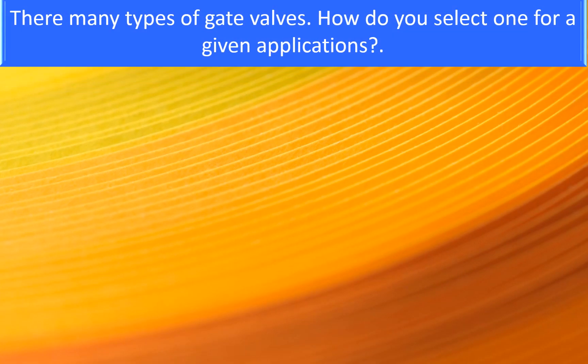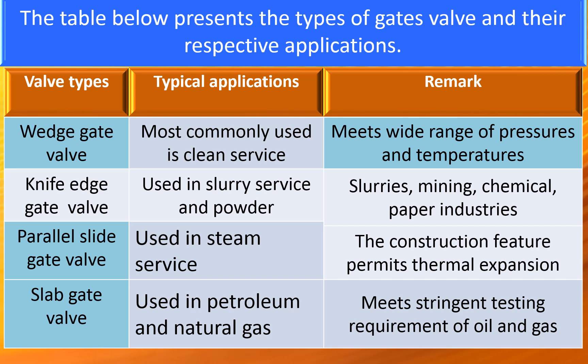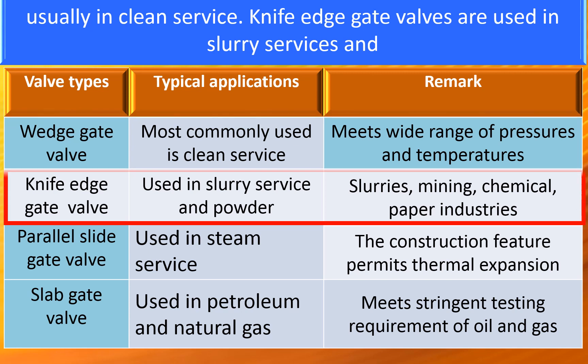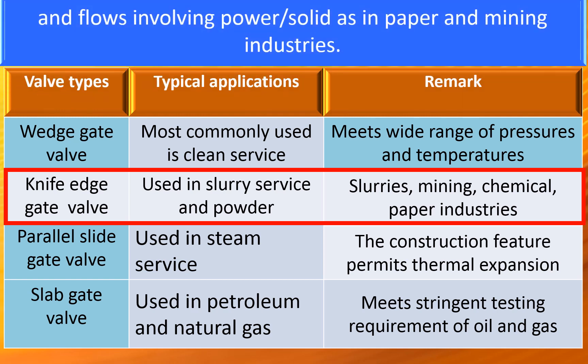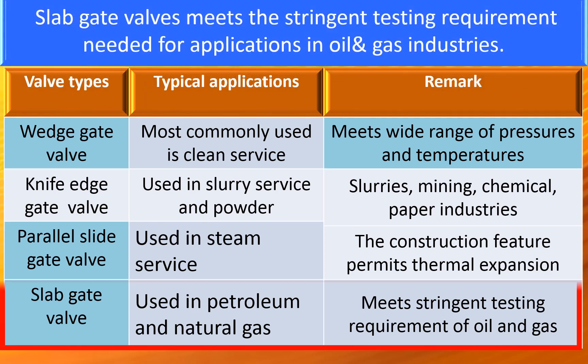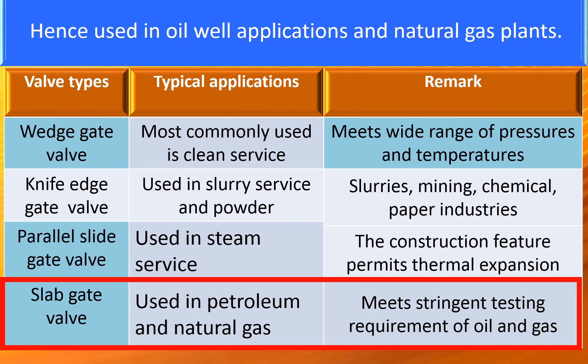There are many types of gate valves. The most commonly used type for general application is the wedge gate valve, usually in clean services. Knife edge gate valves are used in slurry services and flows involving powder or solids, such as in paper and mining applications. Parallel slide gate valves have thermal expansion capability and are used in steam services. Slab gate valves meet stringent testing requirements needed for applications in oil and gas industries, oil-well applications, and natural gas plants.